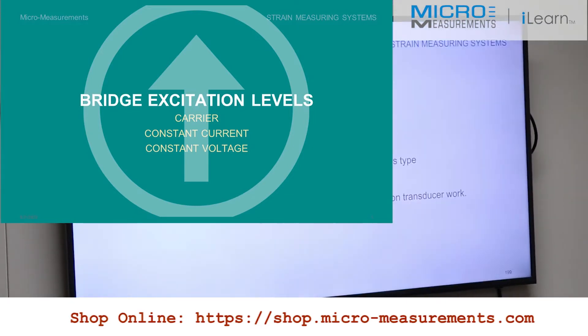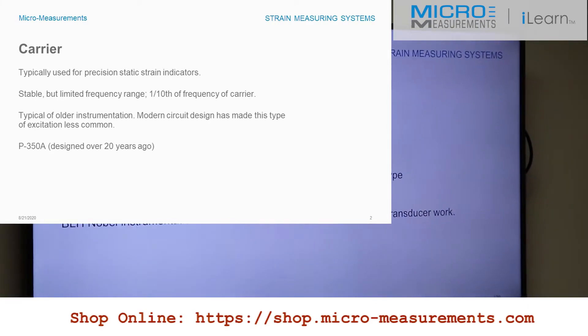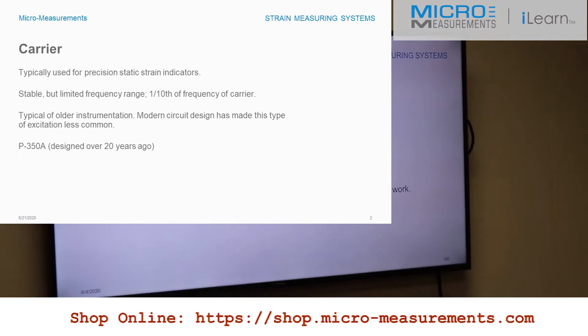Carrier excitation, for those of you who are older and might remember it, is similar to the transition from AM radio — lots of static, lots of noise — to FM. Frequency modulated, nice smooth music, good frequency response, everything was wonderful. That used the same principles as carrier excitation. You take your excitation, put it as a frequency, then ride your signal on top of it. You modulate it out, you demodulate it, and it can give you very, very stable and very, very accurate measurements.